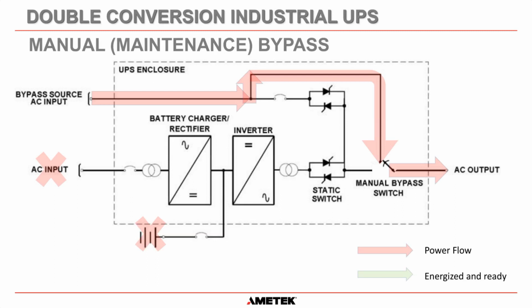And then the final mode of operation, let's say there was something wrong inside the UPS and you switched off the AC input, you've switched off the battery, and what you want to do is get the system into what's called manual bypass. Therefore, we're going to the bypass source, but not through the static switch anymore, because maybe we want to do some repairs on that static switch. We are going around that static switch through the bypass switch. And this bypass switch is a make before break switch. What it does is it just goes from this position here over to this position here. It makes the connection and then it breaks that connection. So once again, your load circuits will not see any power interruption whatsoever in this situation.